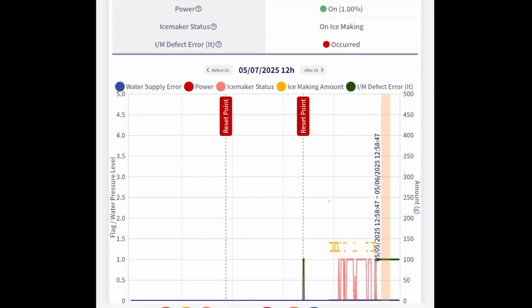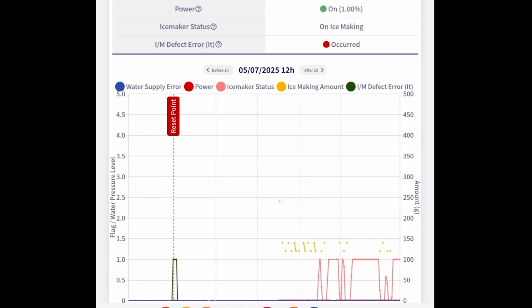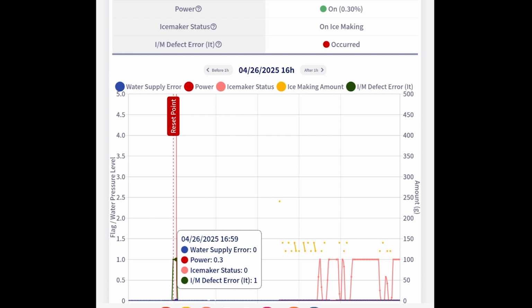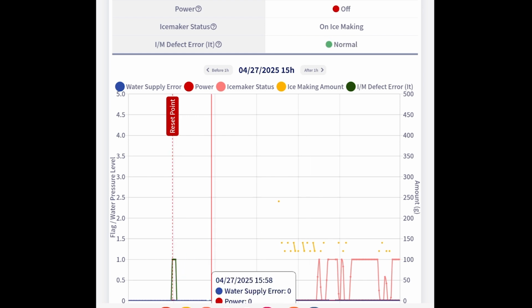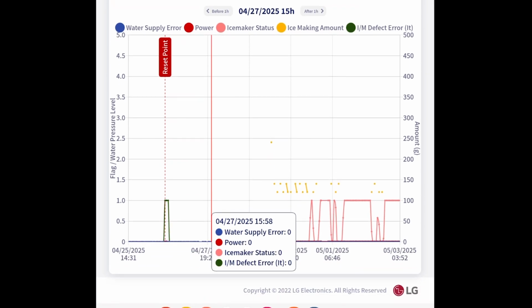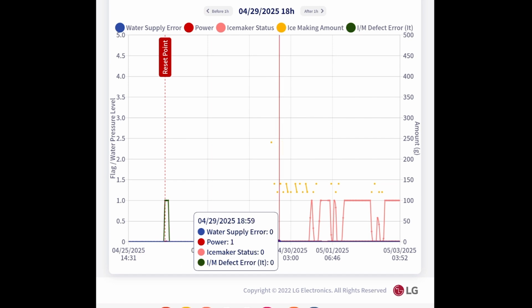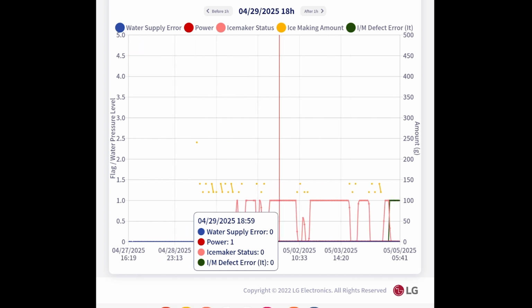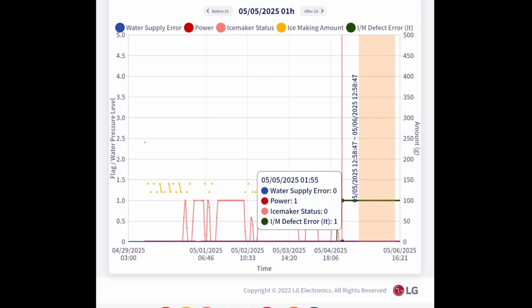So first I'll show you how the error codes display on the ice maker graph. If you look here, this one has an IT error code. Let me make this a little bigger. So this area to the left, where it has this raised dark green area, see how when I click it, it says IT1. That means that there was an IT error code, which is an indoor ice maker error. After that, if you click beside it, the customer actually powered the unit off. And then if we click back over where they turned it back on, it actually started making ice again. You've got your yellow dots, you've got your pink raised bar, so it's filling the bucket. And then again, we get an IT error code. And after that, there's no more action from the ice maker. So most likely that motor on that ice maker went bad, and that ice maker will need to be replaced.